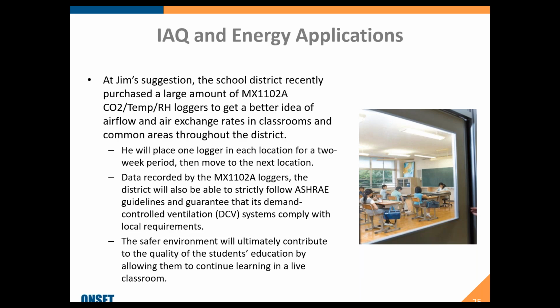So what they did is they bought a good amount of the CO2 loggers so they could place them in these classrooms when they're occupied. They leave them there for 2 weeks and then move them to the next room. It gives them a rough idea of what's going on, and it shows those critical spaces that need attention. They're also able to see that they're falling within the ASHRAE recommended guidelines.